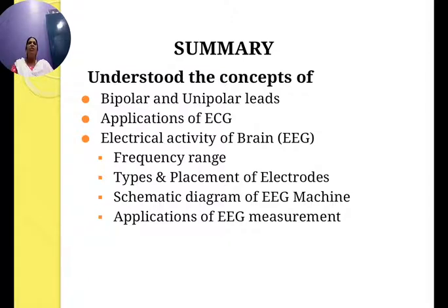Channels. The EEG is recorded simultaneously from an array of many electrodes. The record can be made from bipolar or monopolar leads. The electrodes are connected to separate amplifiers and writing systems. Commercially, EEG machines have up to 32 channels, and 8 to 16 channels are most commonly used.